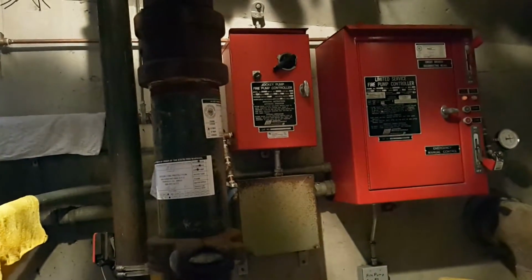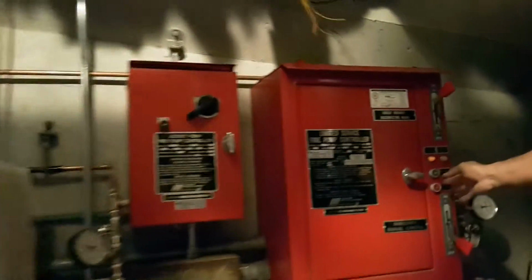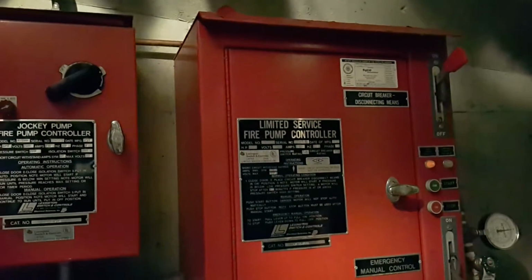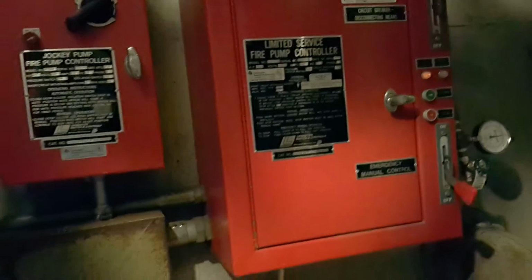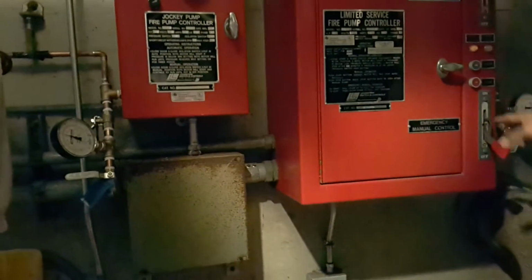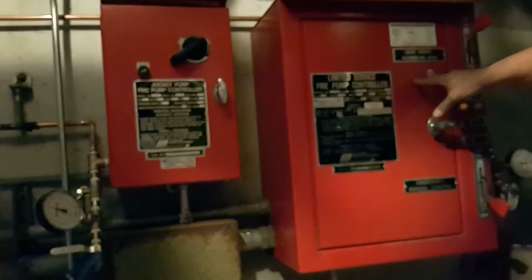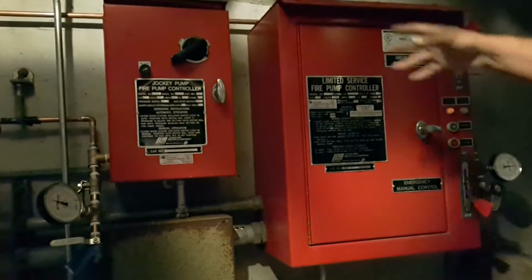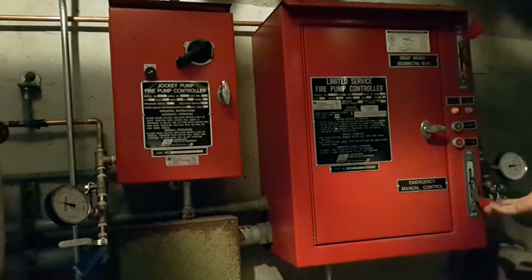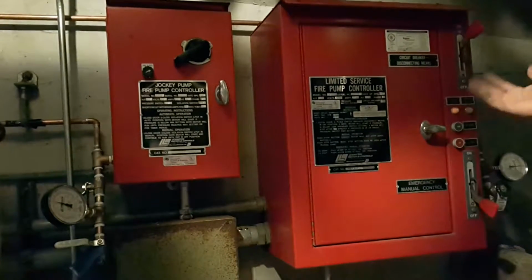Alright. And that's basically it. This is our fire pump on and off. Fire pump start and stop. There's a difference. On means, of course, you have power. Start means you turn the fire pump on, and stop means fire pump stop. This is your emergency run right here, in case any of the components fail. What this does is it bypasses all the components and sends power directly to the fire pump. But when you activate it, you gotta hold it while it's running.